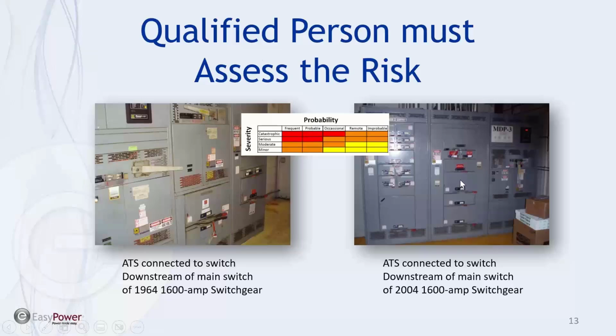The manufacturer recommends a 5-year maintenance plan. So you have a main breaker that requires load testing, and that's not been done in 18 years. So there's no arc flash level that we know of, and there's a breaker that we don't know if it's going to trip in the time current curve it's supposed to. This one has fuses. It's got a switch, but it's got fuses. The fuses don't require maintenance. Those are going to be protective, and it's been maintained. So now I just shifted. I'm now saying I'd much rather work in the 1964 switchgear than I would in the 2004 switchgear.